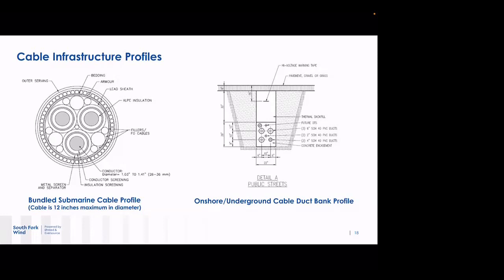This is a big difference from an overhead power line, where for reasons of electrical isolation, the conductors must be spaced far enough apart to avoid any kind of flashover. Here, in the submarine cable configuration, the cables are insulated from one another, so they can be placed very close together. This close placement allows the magnetic field from each cable to partially block the fields from the other cables, resulting in very, very low magnetic fields around these cables.